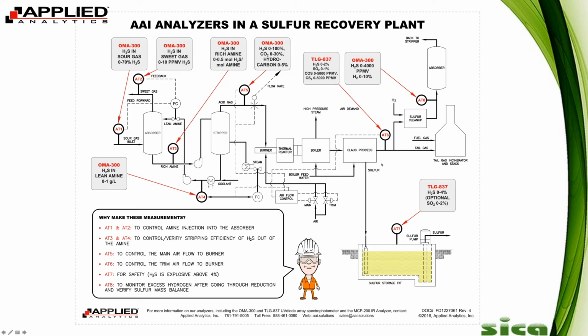And then next we have H2S and hydrogen in the TGTU, which is the tail gas treatment unit. This is not in every single SRU, but it's in most from what I've seen. It's basically a process after the tail gas process that takes all the H2S and SO2 that was not converted and recycles it back into the process. That's pretty much what the TGTU does. And what we do in there is measure H2S and hydrogen. Those are very common applications in the TGTU. People often ask for those two things.